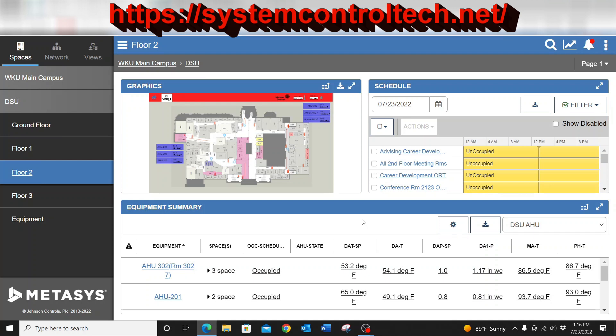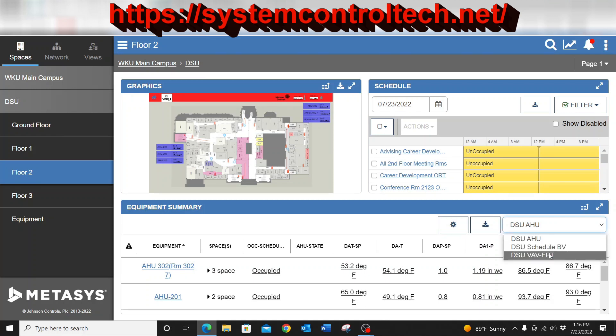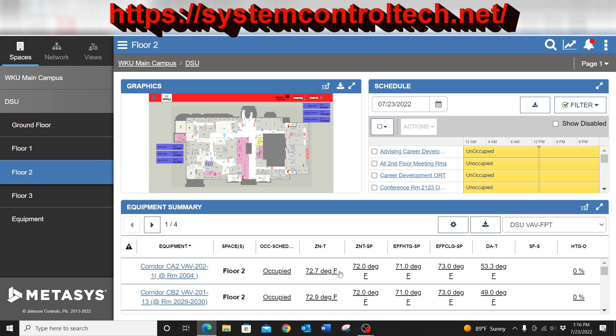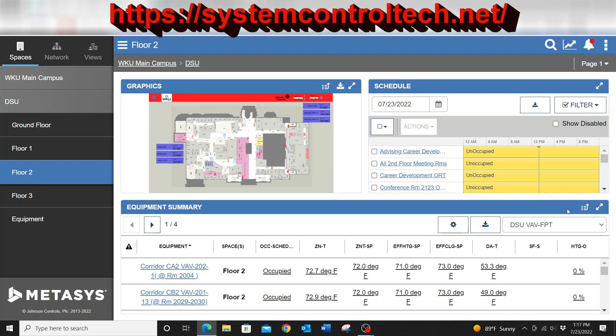What we're going to do here is imagine if I was needing to change the common set point on an entire floor of VAVs. Currently the set point on these boxes are at 72 degrees. However, if for whatever reason I needed to raise or lower that, I can use advanced search and reporting to accomplish this task.